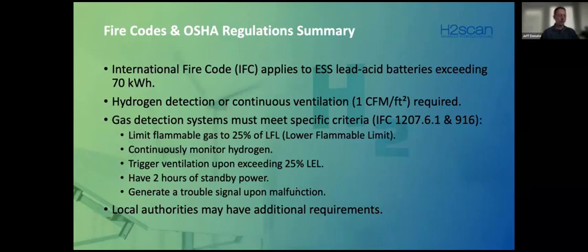One thing I always caution about is that these are typically adopted by the state. However, local authorities are able to add to, but not remove from, the adopted state code. And if you want the reference for that, that's written in either the home rule legislation or in the state constitutions. They have a provision for home rule. Home rule basically states that you can be more strict in a local jurisdiction, but you can't be less strict than the state adopted state code.